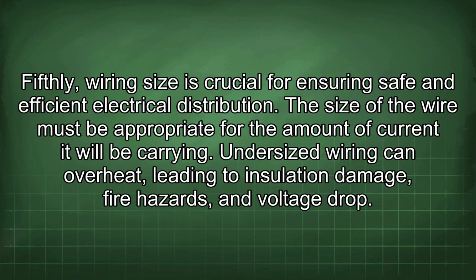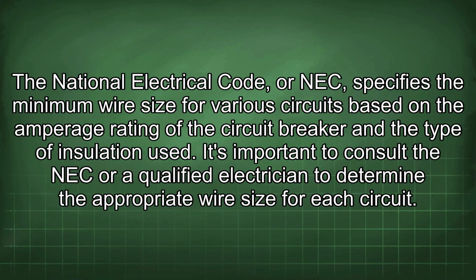Fifthly, wiring size is crucial for ensuring safe and efficient electrical distribution. The size of the wire must be appropriate for the amount of current it will be carrying. Undersized wiring can overheat, leading to insulation damage, fire hazards, and voltage drop. The National Electrical Code, or NEC, specifies the minimum wire size for various circuits based on the amperage rating of the circuit breaker and the type of insulation used. It's important to consult the NEC or a qualified electrician to determine the appropriate wire size for each circuit.